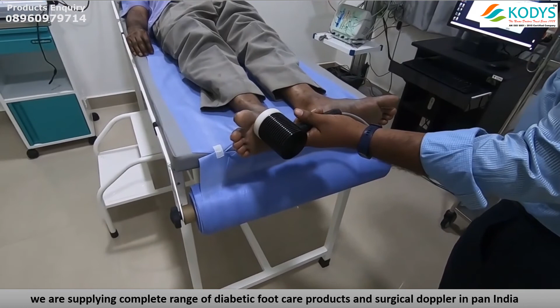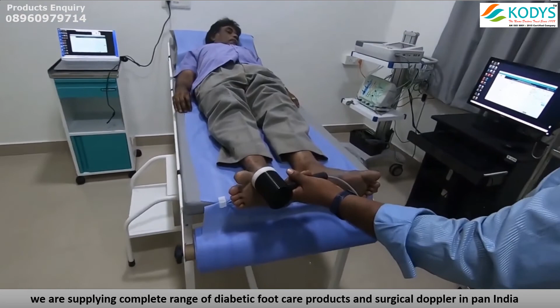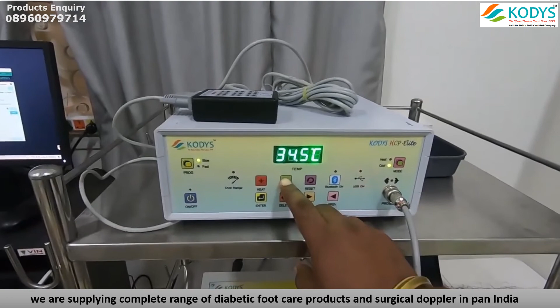At a certain point, the patient feels the cool sensation. At that point, you have to press this enter button. This value will be recorded and shown on the testing screen. In a similar way, we can do it in the next portion. After the testing is completed, it will switch back to 34 degrees Celsius and give the beep. Then you have to place it on the next place, and when you press this cool button, the temperature of the sensor will reduce normally. At a certain point the patient felt the cool perception. There we press this enter button. This will save the values.